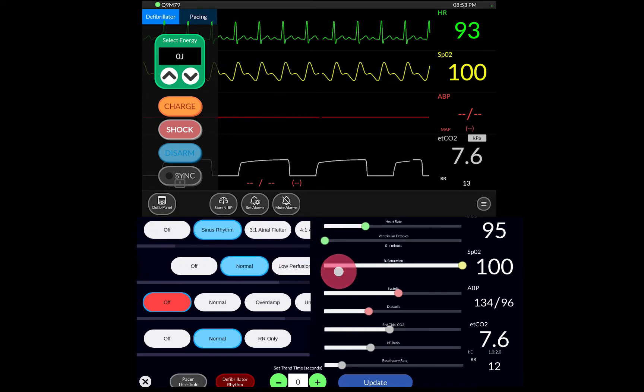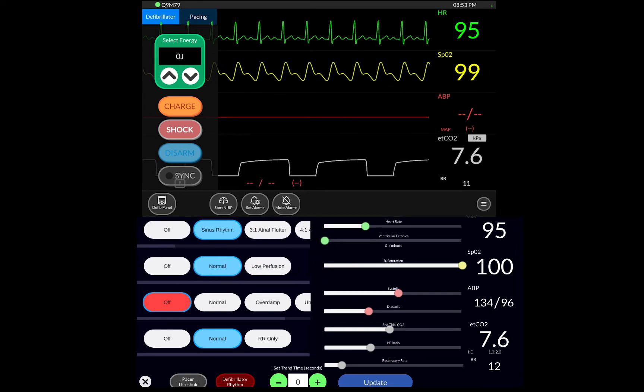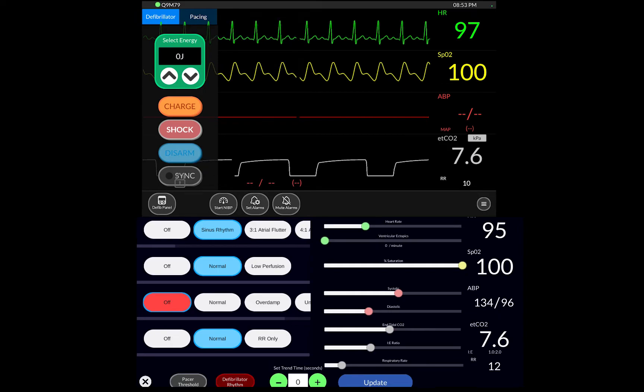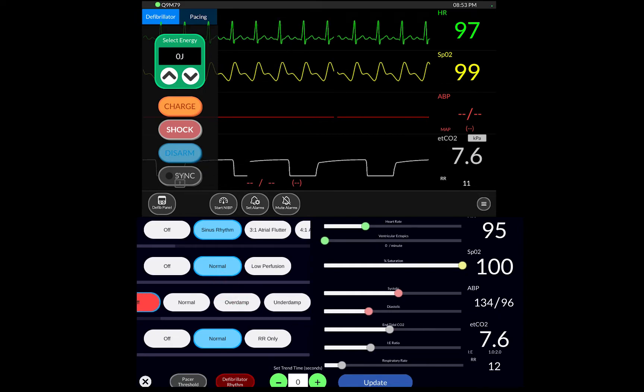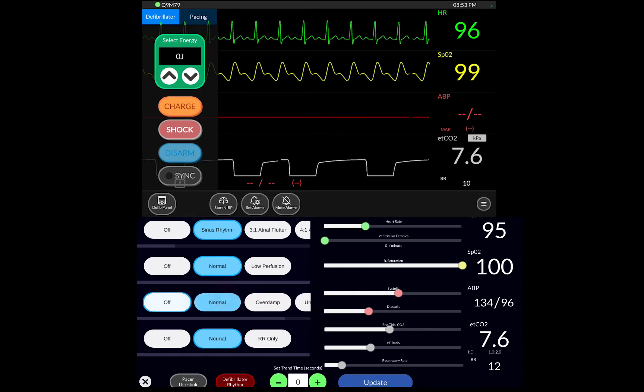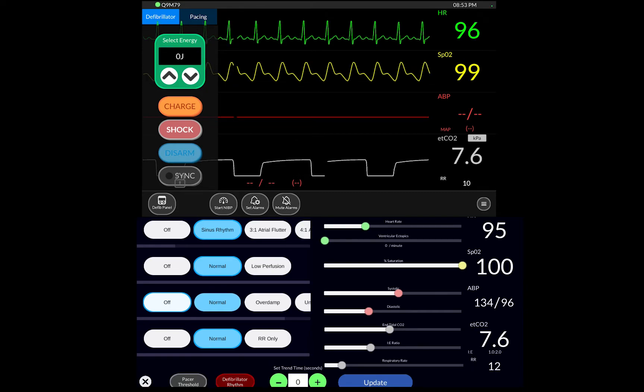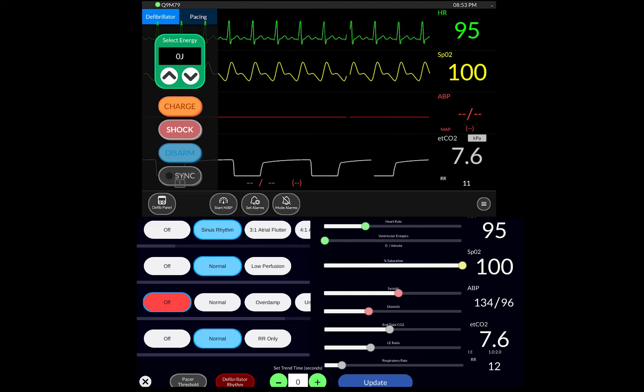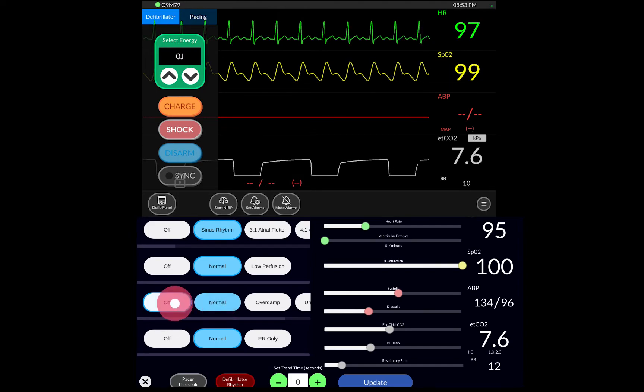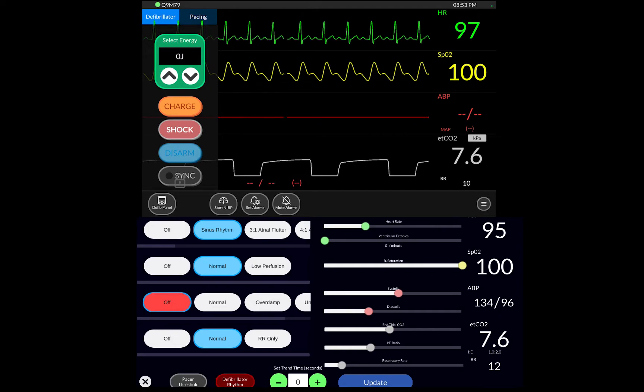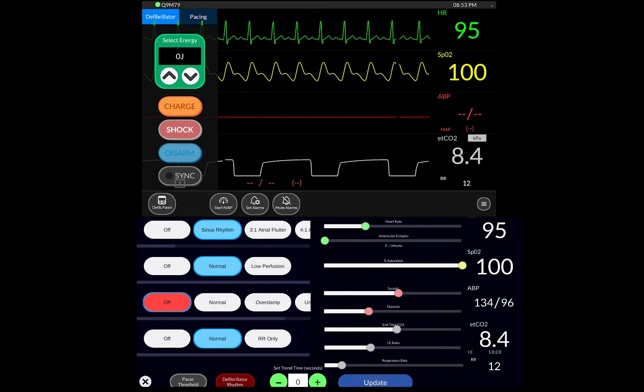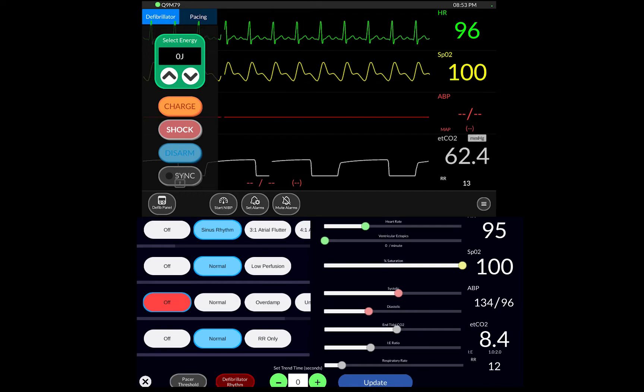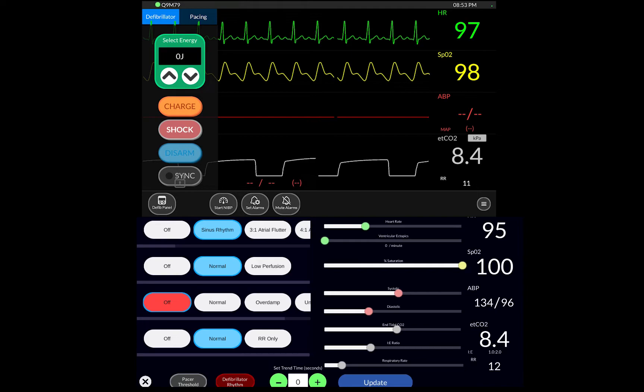Then there's the saturation. Then there's the arterial BP or if you have an A-line, but if you hit normal on this and update it's going to give you an A-line on the monitor and you probably don't have an A-line on the patient. You can't then remove it. So don't click on that normal and update. In terms of the ETCO2 you can just control it like this. It's important to see on the monitor that it starts on KPA, not millimeters of mercury.